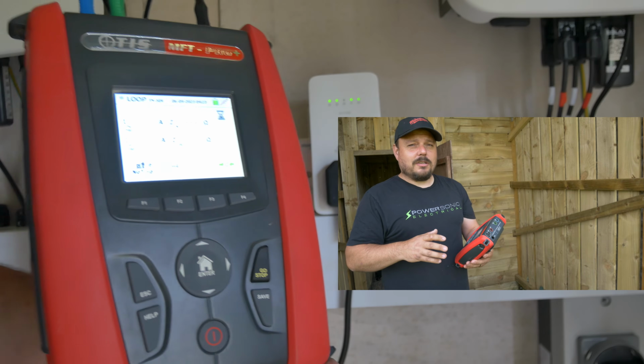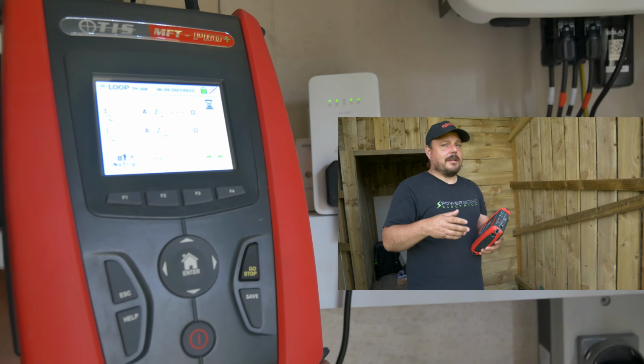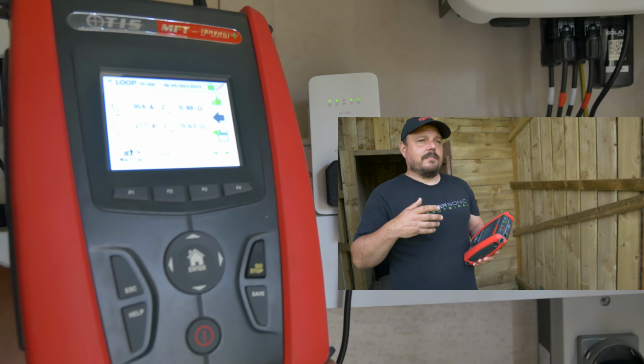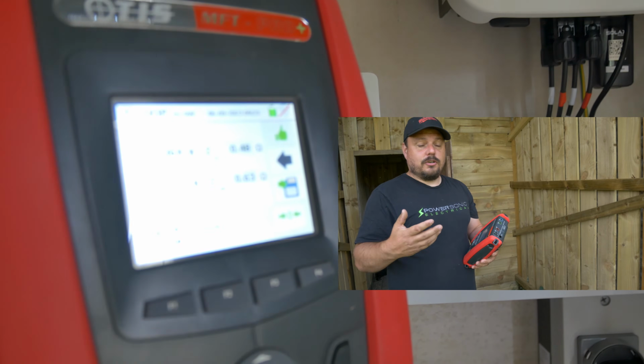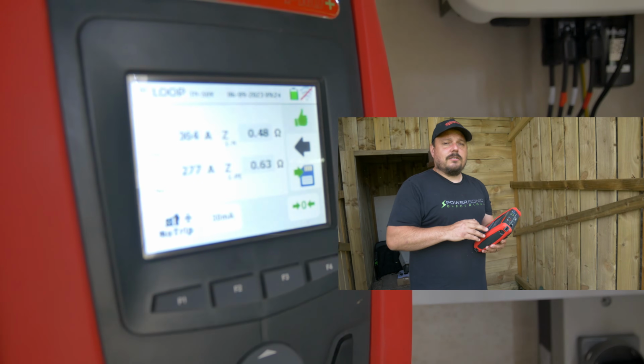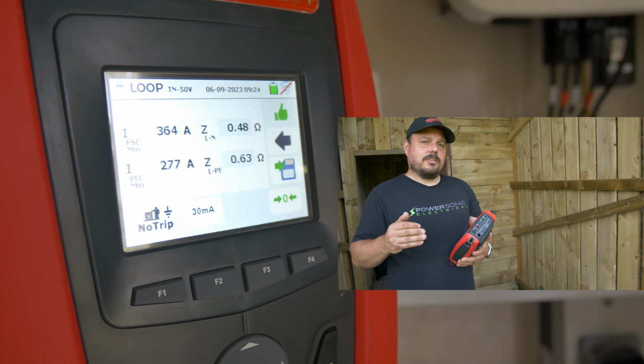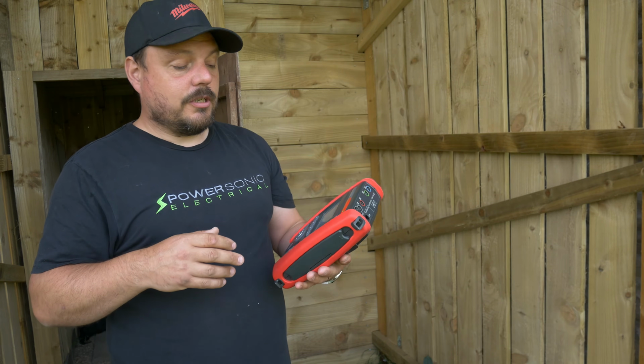It will do a power quality analysis combined with the clamp that I'll show you in a minute, so you can see if the quality of your supply is of good order. It'll do a leakage current measurement, so if you want to do earth leakage current measurement from the MFT, that will do this as well.